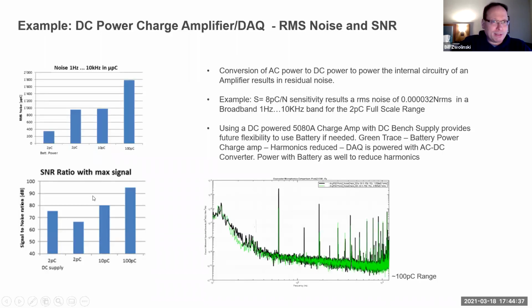So when using DC power, charge amps, signal conditioning and data acquisition, we reckon that you can get upwards of, I don't know, 6, 7, 8 dB improvement in noise just by using battery power. So a lot of times we'll recommend to customers and end users, hey, look, really consider using a battery, because a battery will reduce the overall noise, but it'll also take away any other harmonics caused by the AC to DC power conversion process. When you're looking at harmonics of test articles, it sometimes becomes hard to separate harmonics of AC to DC power conversion from harmonics of actual mechanisms, okay?